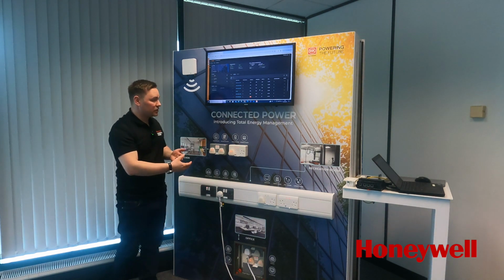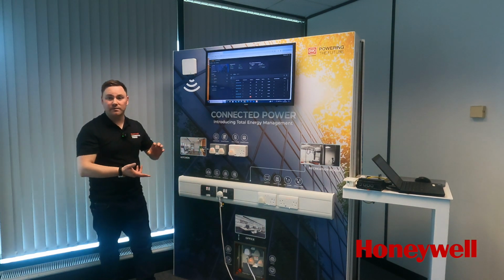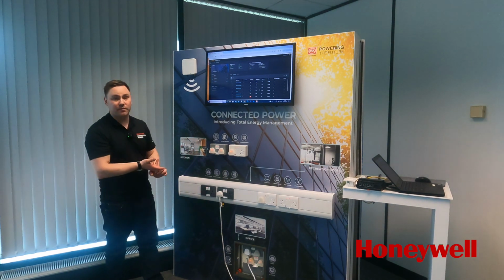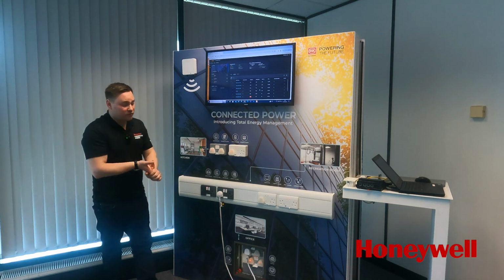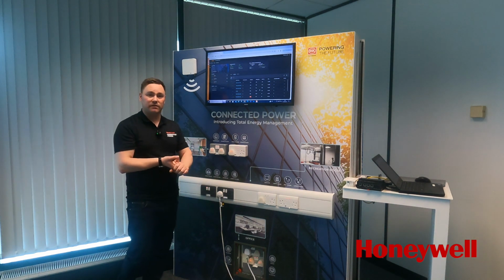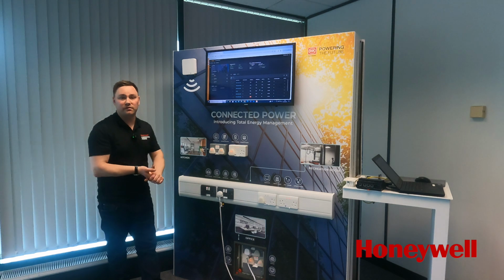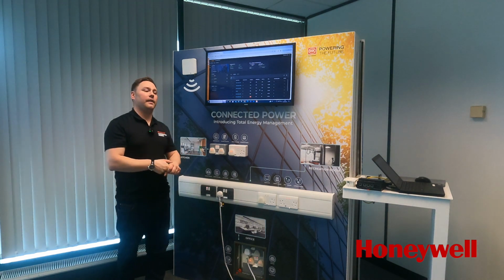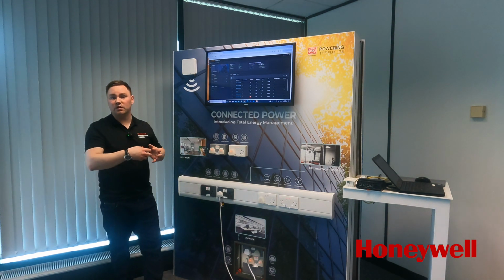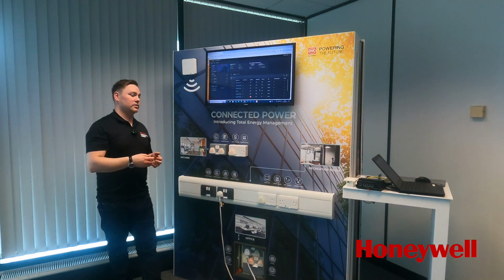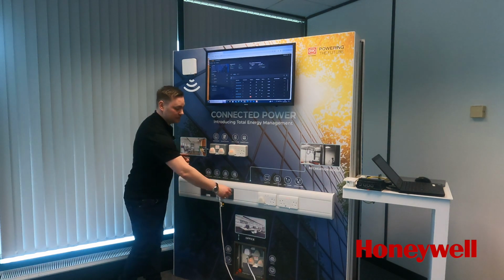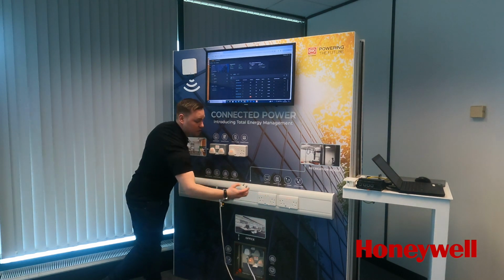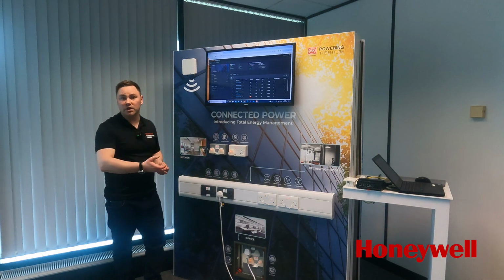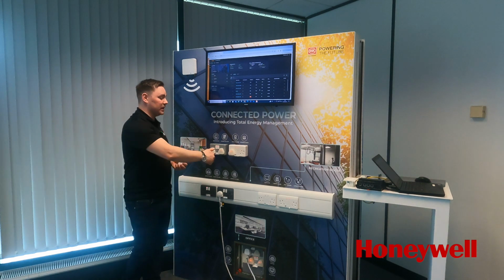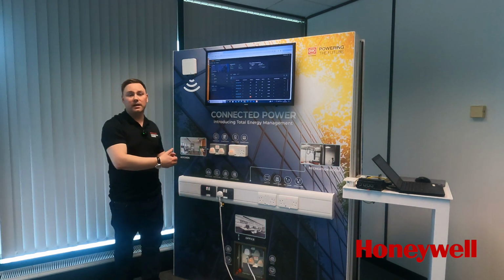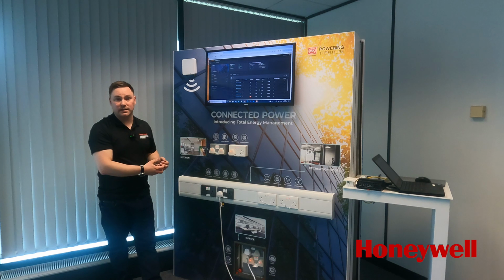With regards to the system as a whole, we have the temperature sensor in there. The reason we want the temperature sensor is that there are over 20,000 commercial fires a year, caused by a potential loose cable in the back of the socket, or sometimes the actual plugs themselves, where it has worked loose over time. So we have built in a temperature sensor that monitors the ambient temperature in the back of the socket.